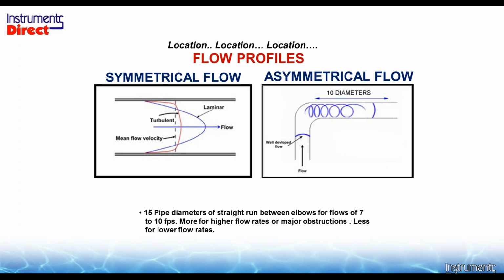So step one, you need to have X amount of straight run of pipe. Nothing unique here. Most flow meters require the same amount of straight run of pipe. In this case, what we want is a symmetrical flow profile where the flow is the fastest at the center and the slowest near the pipe wall. And you notice there are different elliptical shapes. They're called Reynolds numbers. What we're striving for is, if you were to draw a center line down the center of this pipe, the top half of flow equals the bottom half of flow. This scenario occurs when I have enough straight run of pipe here.